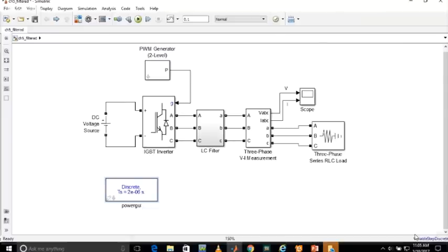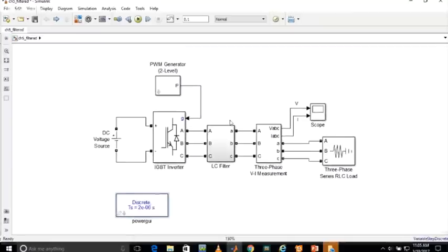So we have to go for a multilevel inverter circuit and then apply the filter circuit. Because after applying the multilevel inverter circuit, the harmonics present in the output of the inverter will be around 12%, 11% if we go for 11 level type. At that point, the harmonics present are only of 11th or 13th order, the highest frequency present in that signal. So the filter requirement for L and C will be reduced. Those components we can get and make an easy, very cheap filter. So this is how we make this whole system in which we have used a filter circuit, and how we can calculate the harmonics present in that signal.